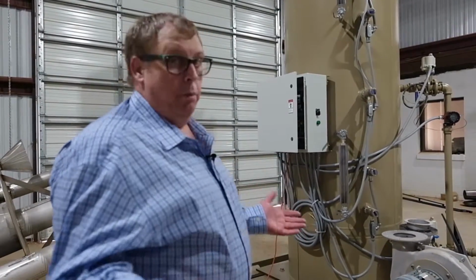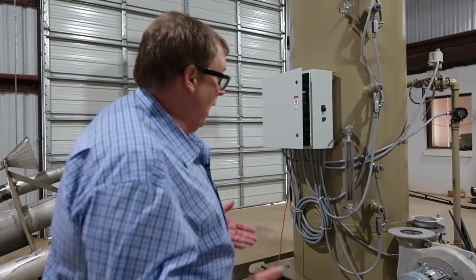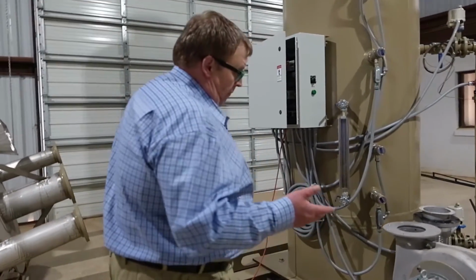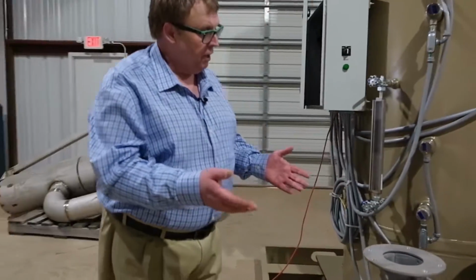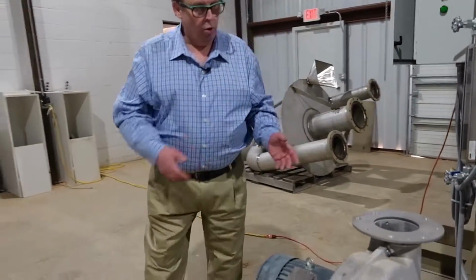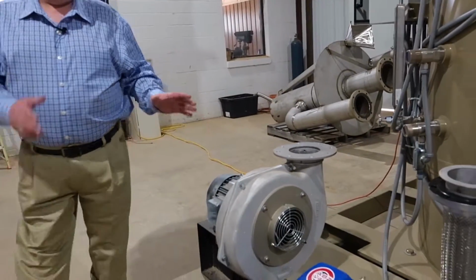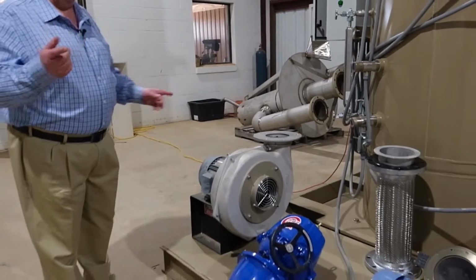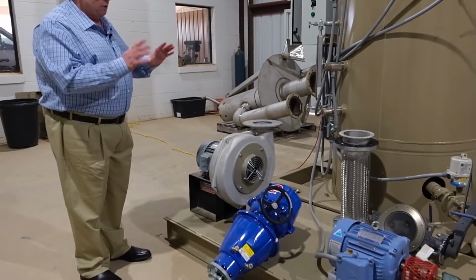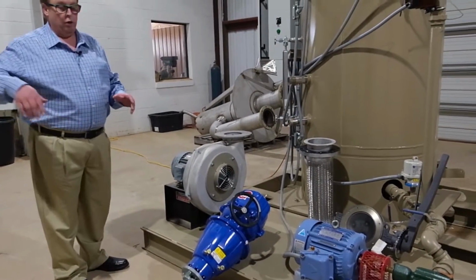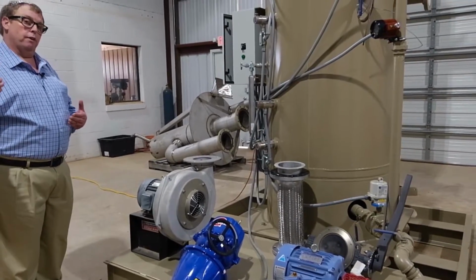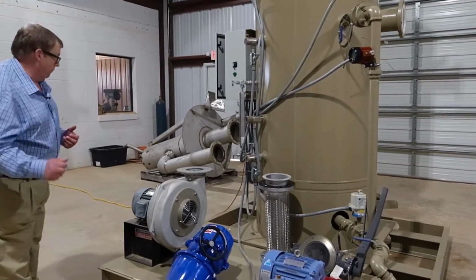First rule is zero emissions, and we achieve that by adding a blower, ESD safety valve, stainless steel hose, and a manual valve, which I'll come back to after I discuss the air-assisted flare tip. But these components are all necessary in order to add the air that's going to be necessary for you to have a smoke-free burn.